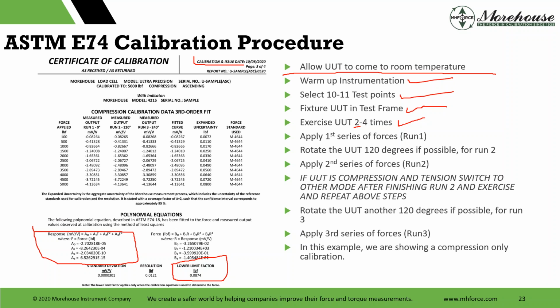We typically will watch the ending zero and see what it's up to. I can tell you in no case do we really exercise only 2 times. It's 3 to 4 for us in our lab. It takes a little extra time, but it really gets the instrument ready, especially after switching from tension to compression. You may need 4 exercise cycles to really warm up the material again or change that material.